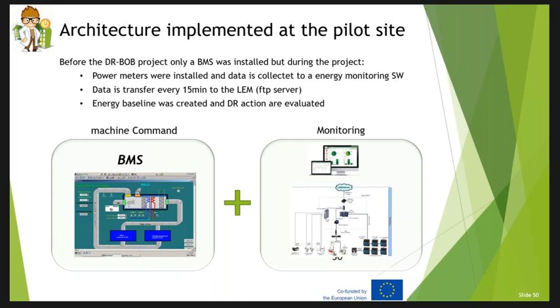The software that we installed, the energy monitoring software, can also read values from the BEMS. So the few values that we have on the BEMS regarding energy or temperature can be displayed on the energy monitoring software, but all the inputs of set points and the whole machine are controlled manually on the BEMS.